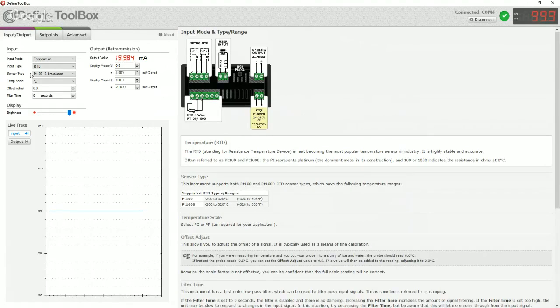So this is the basic startup screen. So we can see up here in the right-hand corner a small black box with the numbers in it. That is showing us the current process input from the Merlin. So that's showing 99.9. I've actually got an RTD sensor in there at the moment. So that's why it's showing 100. So that gives us an up-to-date, a live reading of the Merlin, and it also shows us the set point states. So to set up the Merlin let's go for our application example 2 with the pumps.